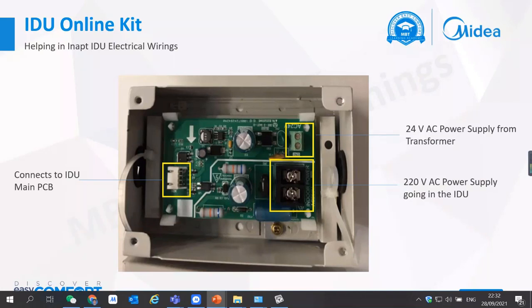How does it work? There's a 24-volt AC power supply that connects to the main PCB of the indoor unit, and there's also a 220-volt AC power supply going into the indoor unit. The kit detects whether the 220-volt supply is going or not. If it detects that it has turned off, it uses the 24-volt AC power supply to supply the indoor unit enough power to send a turn-off command and close its EXV, so that the IDU is effectively turned off from the remote controller, and there's no need for an H7 error code.